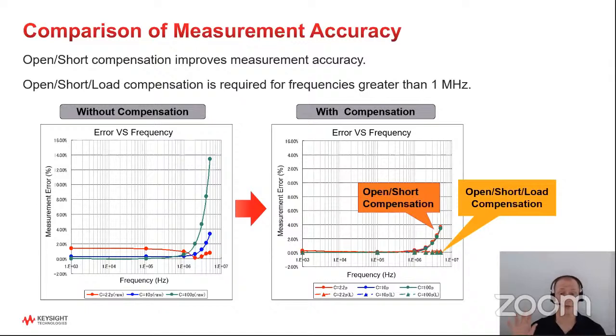Now the graph on the right does a comparison, versus frequency for a device, of the measurement error you get with just open short compensation versus doing the open short load compensation. As you can see from this data, if you don't go above a megahertz, you're probably okay. You don't need to worry about doing the load compensation. But if you're going to go to higher measurement frequencies with your C meter, you probably should consider doing some sort of load compensation. Otherwise, you are going to get increased measurement error as you go to higher and higher frequencies.